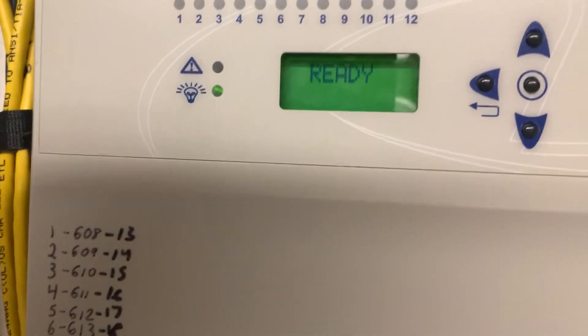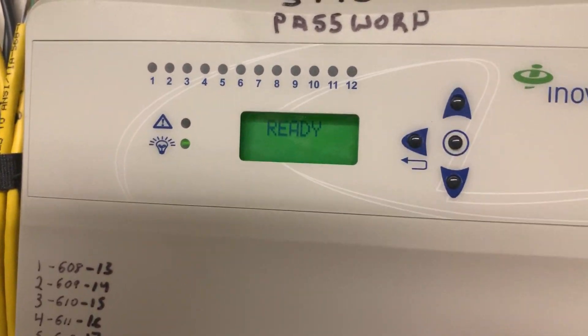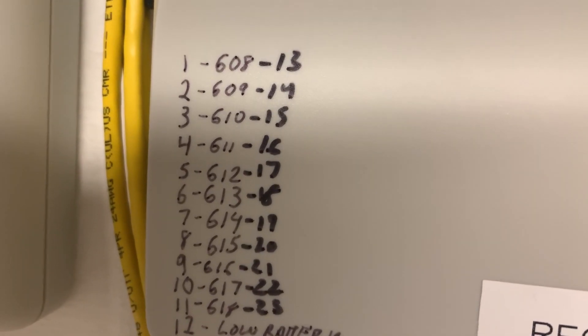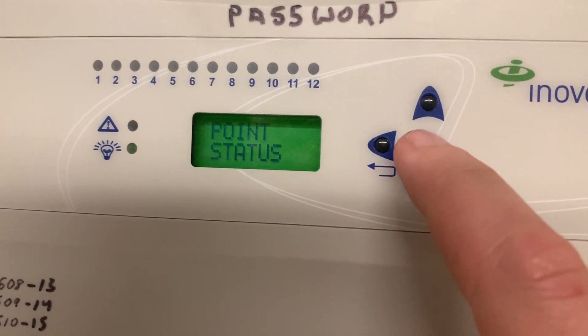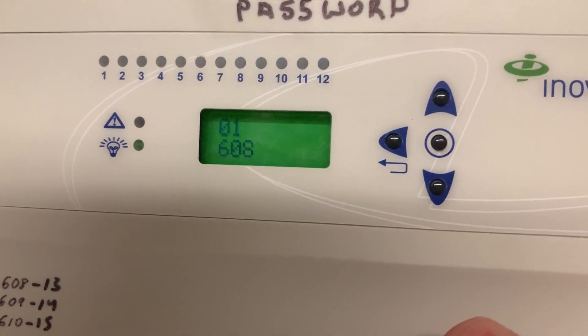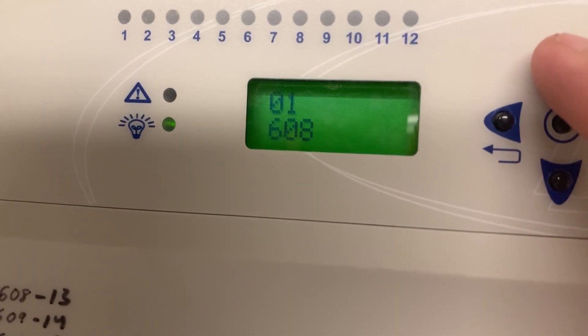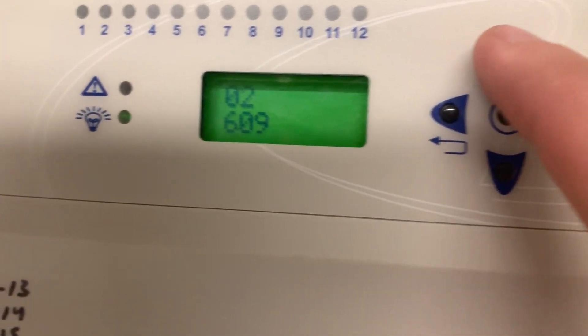But let's say for example you had a red light. What you'd want to do to figure out the problem with one of these 11 transmitters for these 11 rooms is just hit the enter button, go to point status, hit enter again, and scroll up through the points. You can see room device number one is 608, two is 609, and so on.